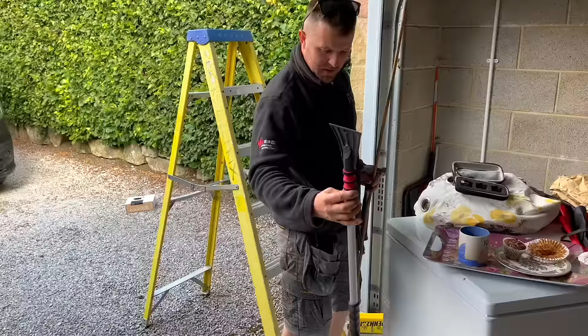Heat is another concern. EV charging leads sitting in shallow metal cable channels can get much hotter than cables in free air. On a sunny day, tarmac can hit 40 to 50 degrees Celsius, which dramatically reduces a cable's current carrying capacity. For example, a 6mm single-phase charging lead rated at 44 amps in free air could be limited to around 25 amps at 50 degrees C once correction factors are applied. And don't forget voltage drop either. The charging lead counts too, especially on longer runs.